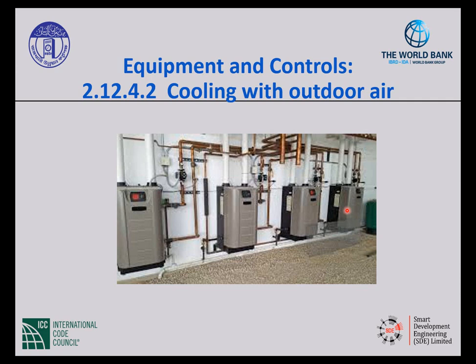So what it's asking us to do is to provide these controlling sequences and controls that allow us to, when the load calls for one, to only have one going and not all 4 of them. When the load increases and now we need 2 of them to serve that load, then 2 come on. And maybe we get up to 3, and maybe we get up to 4. But as soon as the load reduces, we're back down. We're back down. We're back down, right? So it's asking us to really pay attention to control systems to reduce the energy use for when the loads call for it. And that's a lot done through sequence of operation, part load controls, and that sort of thing.